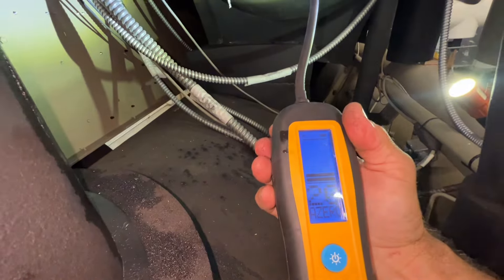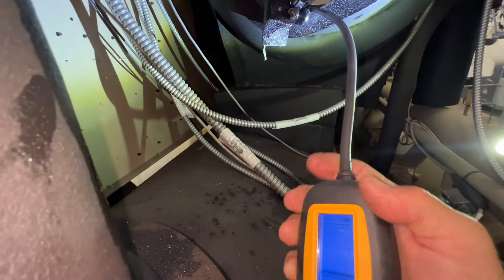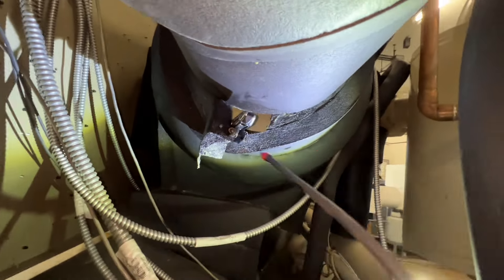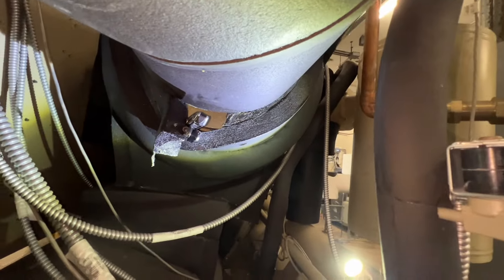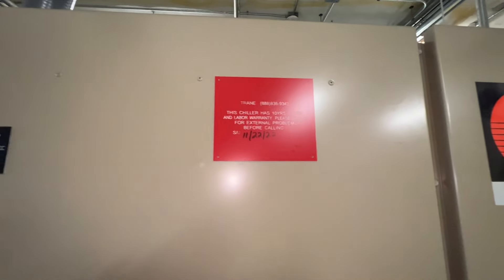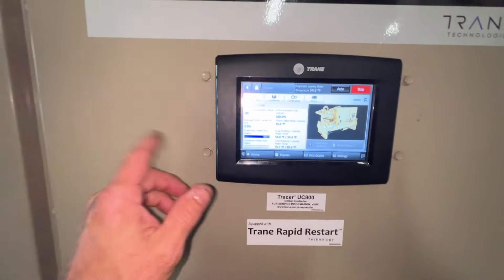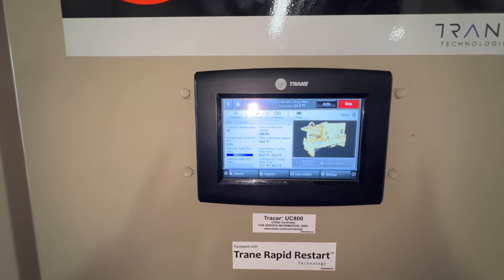It's definitely picking up there. Maybe it's just a flange gasket — they can tighten it up or something. But we've got to call Trane. These machines do have a 10-year warranty on them, parts and labor. Or at least I can let them know — that's about what I think it is.